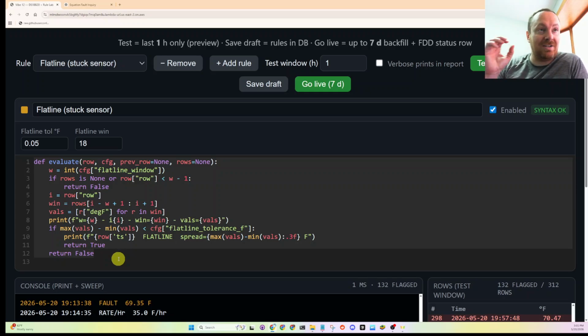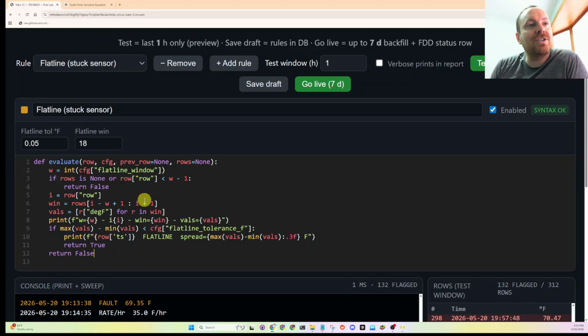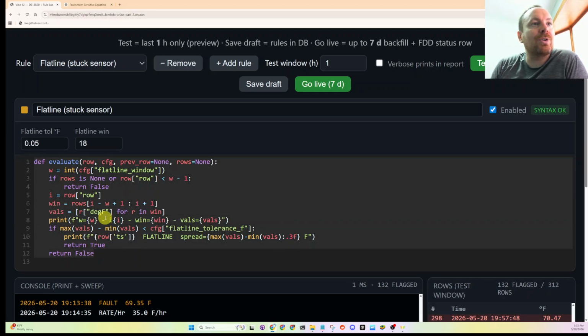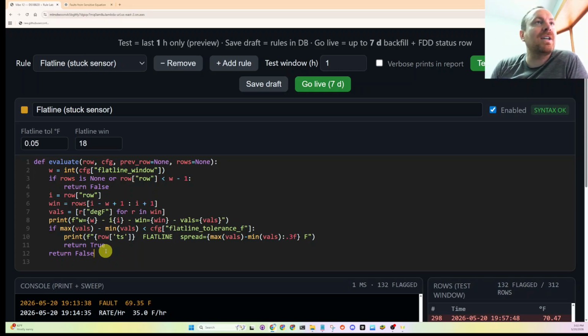So the basic nuts and bolts: the flatline sensor fault is that if the temperature does not change within this window of time, where for us 18 would be 180 seconds I guess, if the temperature does not change by this value, that's a flatline sensor fault. And obviously if this was like a static pressure sensor or something dependent on a fan or motor running, we would be filtering data for that as well.